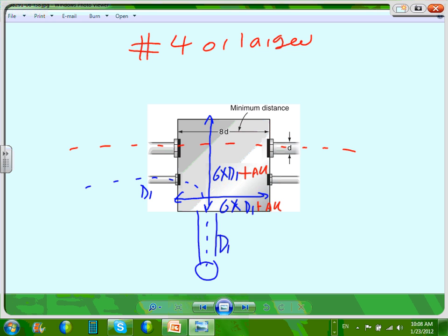And if you have a U-pull, you guys remember the U-pull? The U-pull right here, going this way, will get you a distance of 6 times the largest, plus all others sharing the same wall. And again, I'm going fast through this because we went through it, sharing the same other wall. And of course, the distance between the conduits sharing the same conductors here cannot be less than 6 times the diameter, D1. When Ashley goes and drills a hole in the box so you can put this conduit, you have to make sure your holes are not closer than 6 times the diameter of the 2 conduits.